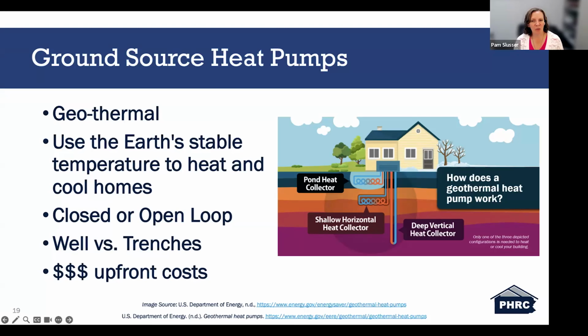However, when you do the vertical loops, which is your wells, which is the other option with the closed loop system as well, then you need to bring in a well driller to drill those wells. They put deep vertical wells into the ground. And so sometimes they might equal out in price, but the trenches and the wells are almost the same. However, with the wells, less piping may be required. You might not need as much piping.